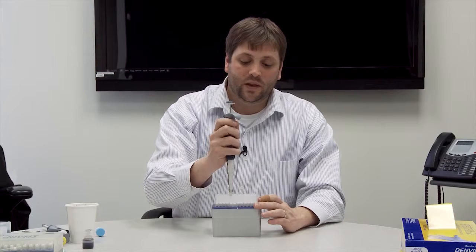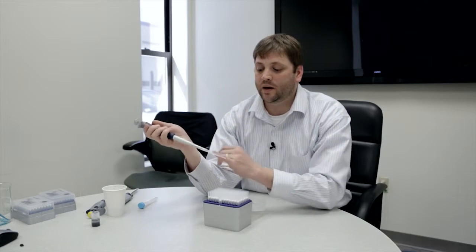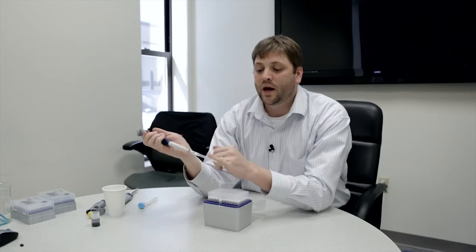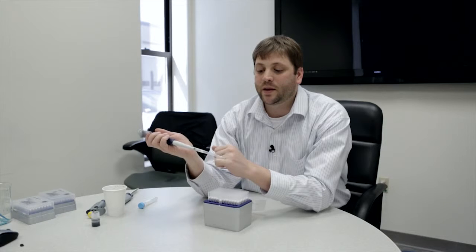The next tip I'd like to talk to you about is our Denville 1000 microliter pipette tip. What's unique and differentiated about the Denville 1000 is we actually give you 250 microliters of extra dead space. Extremely clear pipette tip.